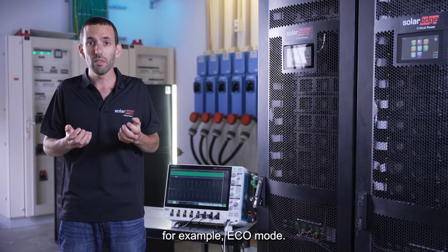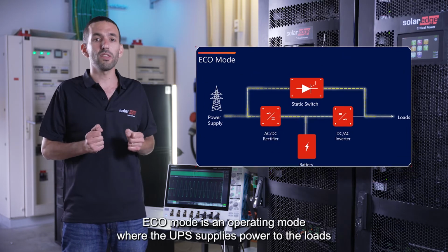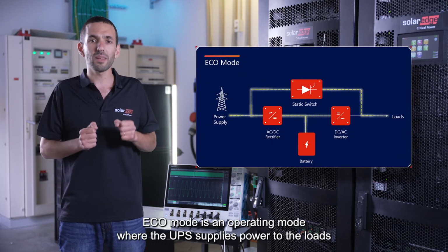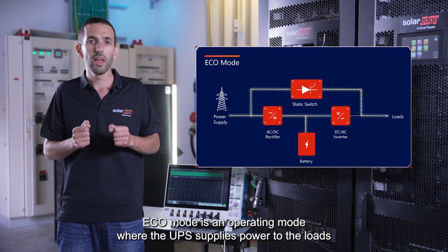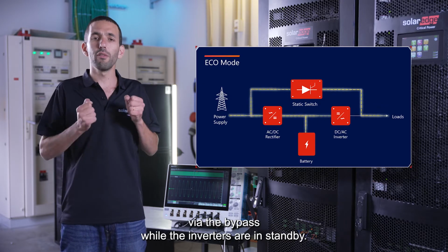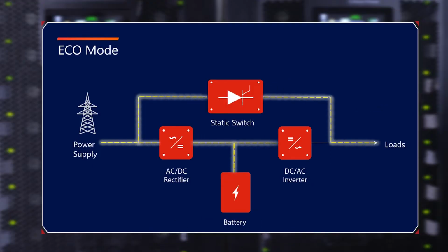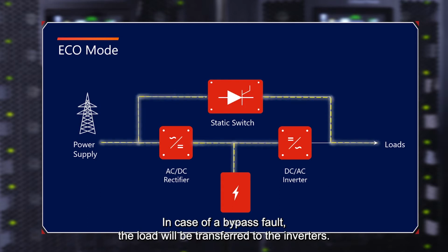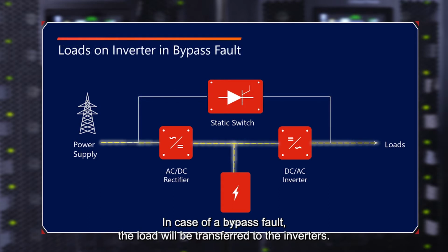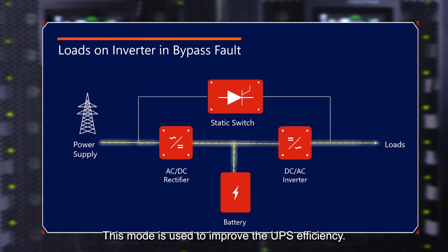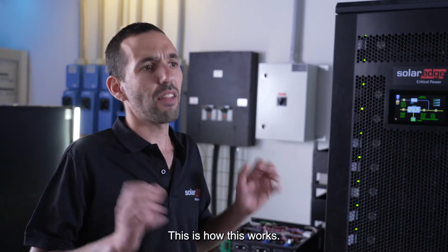For example, Eco Mode. Eco Mode is an operating mode where the UPS supplies power to the loads via the bypass while the inverters are in standby. In case of a bypass fault, the load will be transferred to the inverters. This mode is used to improve the UPS efficiency. This is how this works.